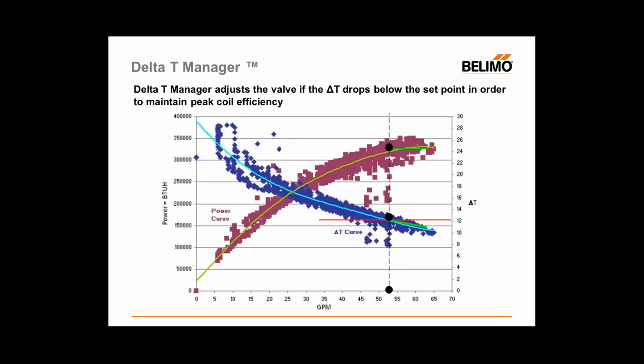So as an example, if I picked 16 degrees Delta T for this coil, I likely would be only able to produce about 75 or 80% of the capacity of this coil, which in some cases might be fine. Might be able to cool a space just fine with that. But in the case of this one, we were looking for the full capacity of that coil, and so 12 degrees F is what we're going to be able to do here.